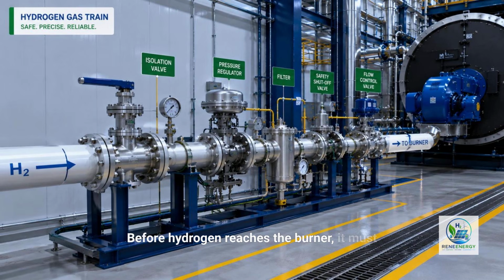Before hydrogen reaches the burner, it must pass through the gas train. This system carefully prepares the fuel for combustion. Pressure regulators ensure hydrogen arrives at the correct pressure. Isolation valves allow operators to safely shut down the system. Filters remove contaminants, and flow control devices precisely meter the amount of fuel entering the boiler. Hydrogen behaves differently from natural gas. It burns faster, has a wider flammability range, and requires specialized combustion controls. Every component in the gas train is designed to deliver hydrogen safely, consistently, and accurately to the burner.